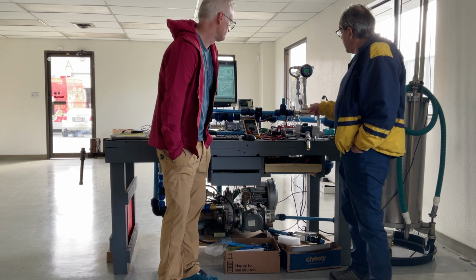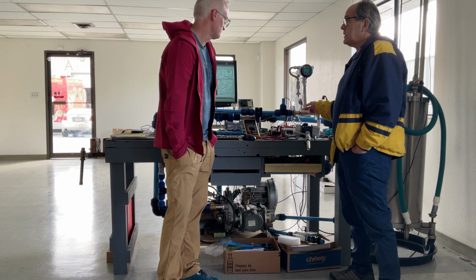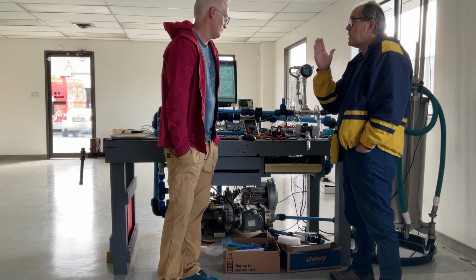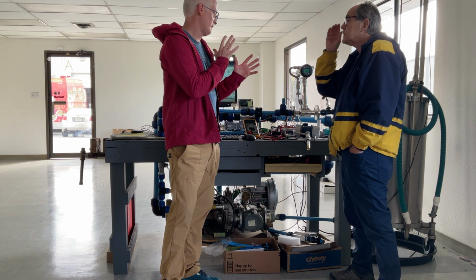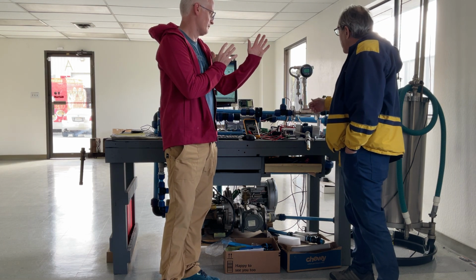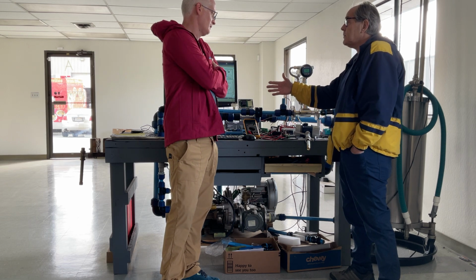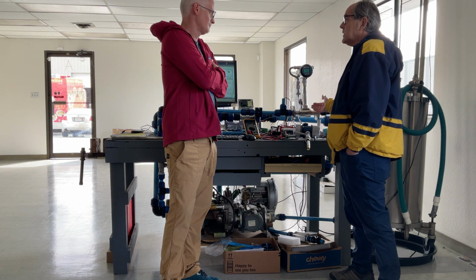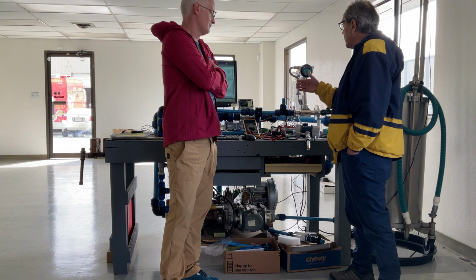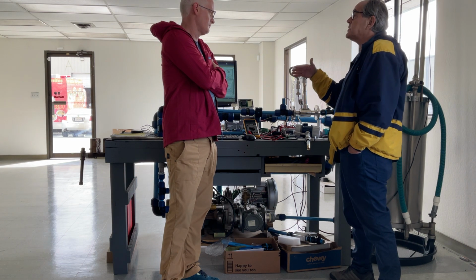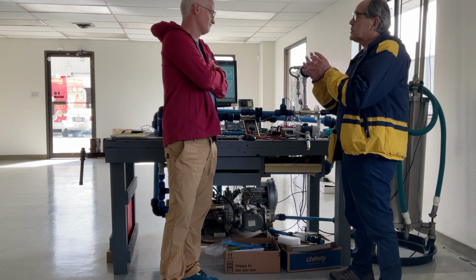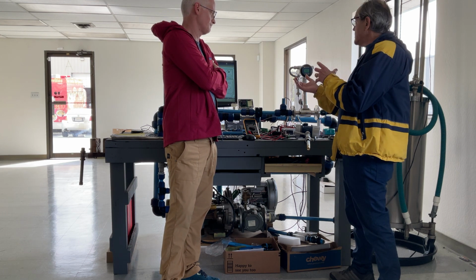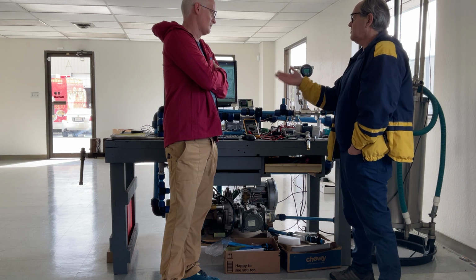Okay, cool. And because the Achilles heel is vibration, because it's a piezo crystal that's sensing that vibration, you can have vibration caused by a pump hooked to this that's vibrating at 3450 RPM, and this thing's vibrating at 100 hertz, and that 3450 is impressed on top of the 100 hertz, causing a complex waveform that we discriminate using digital signal processing to filter out those high frequencies.